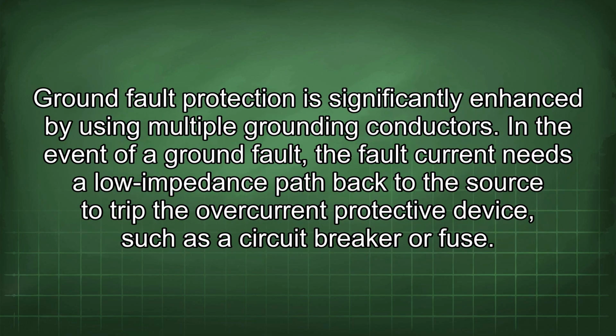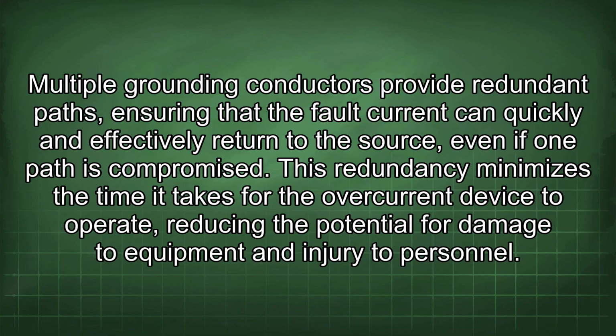Ground fault protection is significantly enhanced by using multiple grounding conductors. In the event of a ground fault, the fault current needs a low impedance path back to the source to trip the overcurrent protective device such as a circuit breaker or fuse. Multiple grounding conductors provide redundant paths, ensuring that the fault current can quickly and effectively return to the source, even if one path is compromised. This redundancy minimizes the time it takes for the overcurrent device to operate, reducing the potential for damage to equipment and injury to personnel.